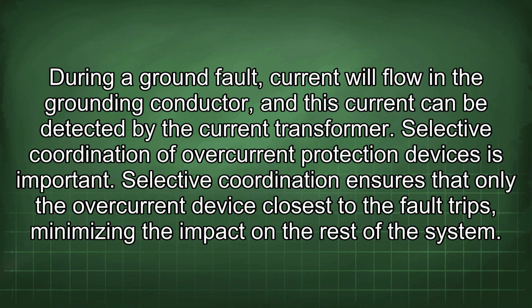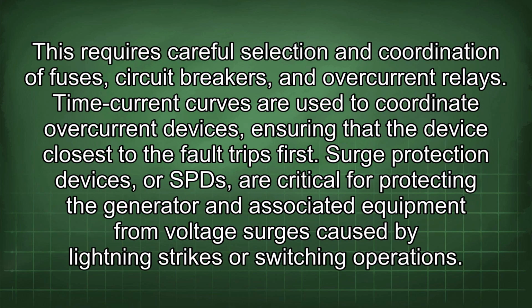Selective coordination of overcurrent protection devices is important. Selective coordination ensures that only the overcurrent device closest to the fault trips, minimizing the impact on the rest of the system. This requires careful selection and coordination of fuses, circuit breakers, and overcurrent relays. Time current curves are used to coordinate overcurrent devices, ensuring that the device closest to the fault trips first.